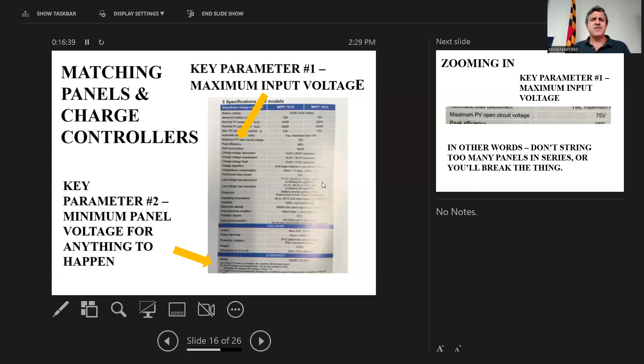So, this particular product that I got the spec from says 75 volts - they don't want to see more than 75 volts on the input coming from the panels, and it says open circuit. What that means is, if the panel is sitting there with nothing else happening, connected to the unit with no load on it, that's the maximum value it would ever operate at. Now, this panel is never going to be above 24, so you can parallel this panel and this particular product will handle it easily. Or you can put two of them, maybe three, in series, but with three in series you're going to get very close to that maximum. So that's something to pay attention to.